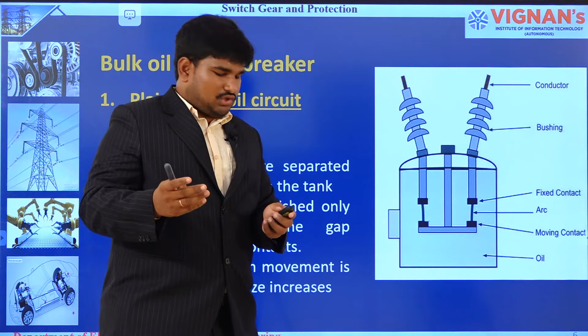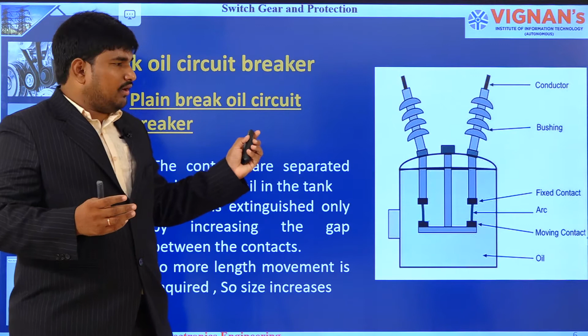If you are using it for higher voltages, the arc will be very intense. To quench the arc, we need to increase the length of the gap between the contacts, so it is not useful for high voltages. The arc is extinguished only by increasing the gap between the contacts. As the length increases, the size of the tank also increases, so the cost increases. That is the basic disadvantage of the plain break oil circuit breaker.